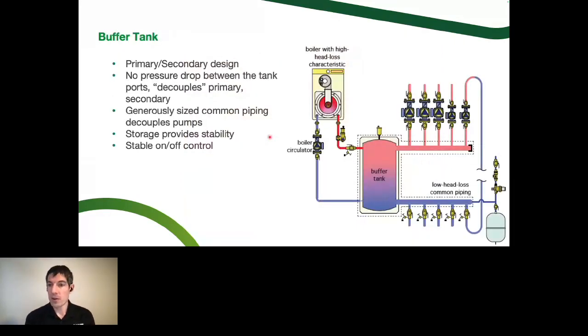Okay, option number 2. Let's say that we are going to go with a buffer tank. There are a bunch of different reasons that we might be using a buffer tank. One would be, let's say we're replacing a modulating condensing boiler with a heat pump. The heat pump manufacturer may say, you need to have a buffer tank. We can't cycle this compressor 10 times in an hour. That wouldn't be good for a mod con either, but it just is going to void the warranty of the heat pump to not have a buffer tank. I think that is the case with some of the technologies that are on the market right now.